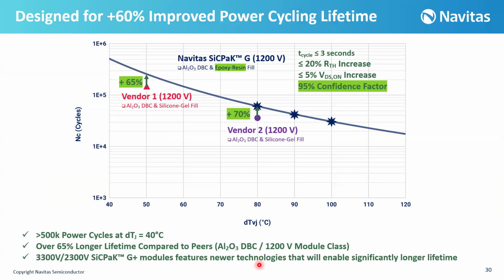And here is a comparison of power cycling lifetime between these two types of modules, with epoxy resin and silicone gel. As you can see, we have more than 65% higher power cycling compared to one vendor, and more than 70% compared to another vendor. It shows over 65% longer lifetime compared to the silicone gel, as I mentioned.